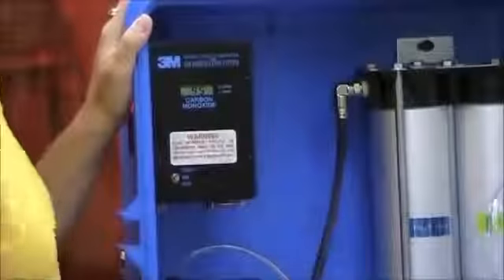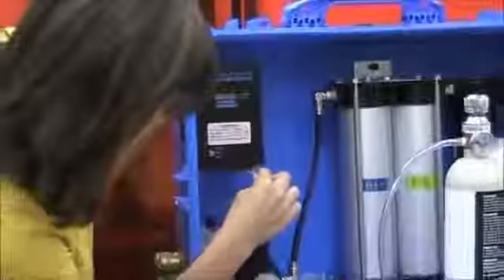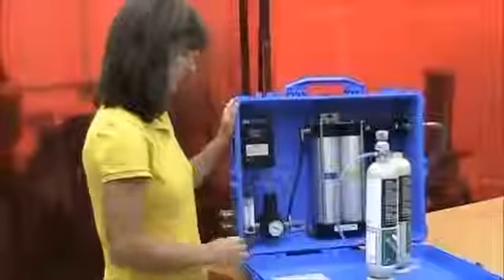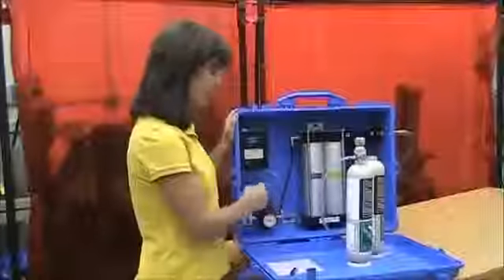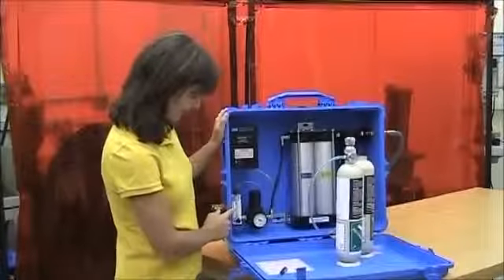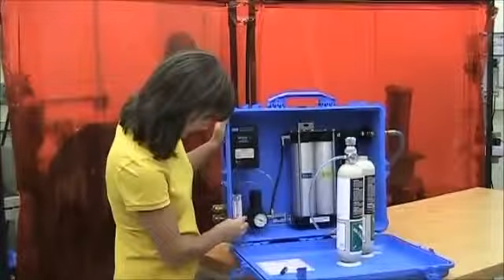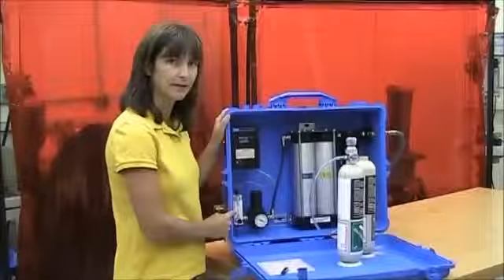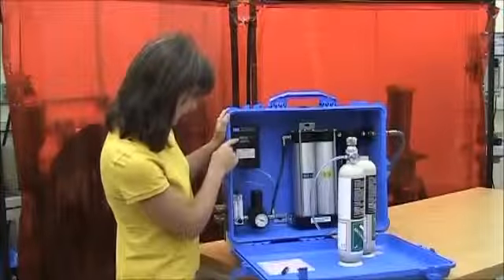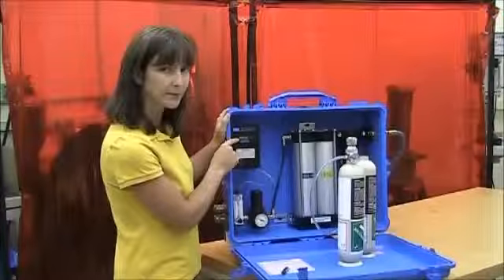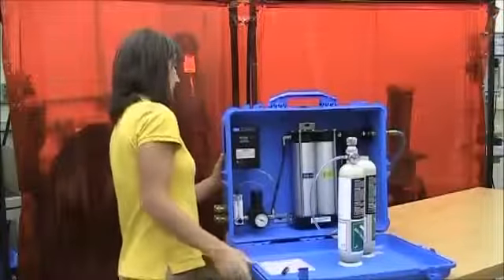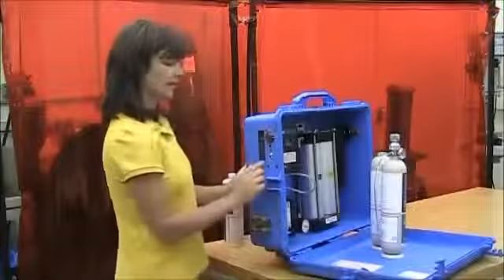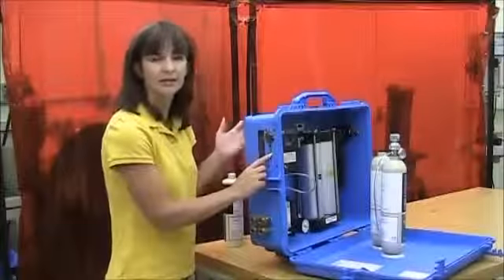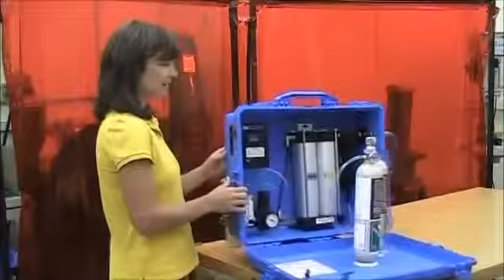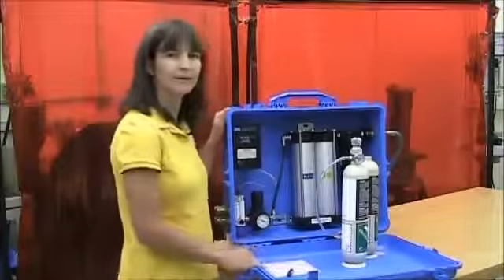Okay? And I'm going to take my gas off, turn it off, reconnect it to my supplied air system. Make sure that the flow of gas here is adjusted so that I'm in the center of the green rectangle. And I'm almost down to below 10 parts per million, and my alarm turns off. And then I should see on the right side of the panel that I'm in normal operating state, the green light's on. So my monitor is functioning properly, and I'm all calibrated, and I'm good to go.